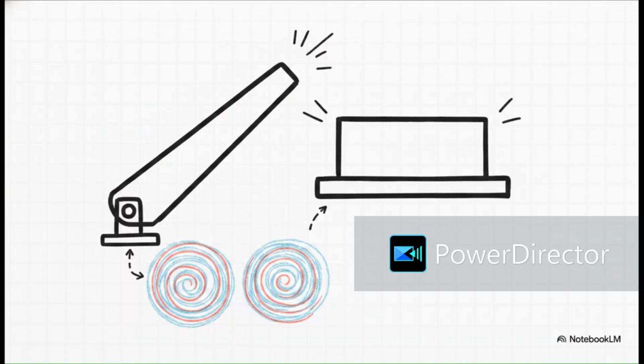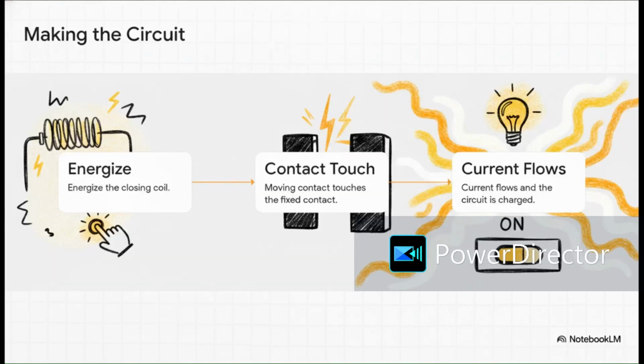To really understand how it operates, I want you to picture a giant mechanical drawbridge. Inside this device, we have a fixed contact that stays perfectly still and a moving contact that raises and lowers to bridge the gap. And this whole movement, it's controlled by the breaker's mechanical muscles, specifically a closing coil and a tripping coil. So here's how those muscles actually work to turn the power on.